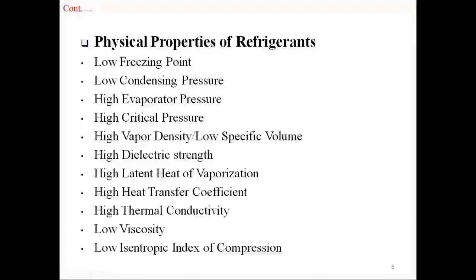Refrigerant should have a low value of condenser pressure, so that power required for compression will be lower, resulting in low operating cost. Refrigerant should have a high value of evaporator pressure; otherwise atmospheric air or moisture will leak into the system. Refrigerant should have a high value of critical pressure; otherwise the zone of condensation decreases. Refrigerant should have a high value of vapor density or low specific volume, so it will require a smaller compressor and condenser tubes of smaller diameter.